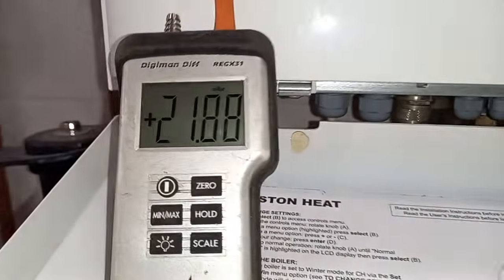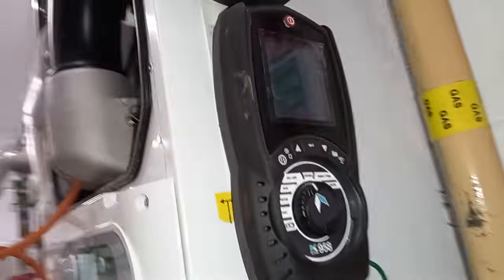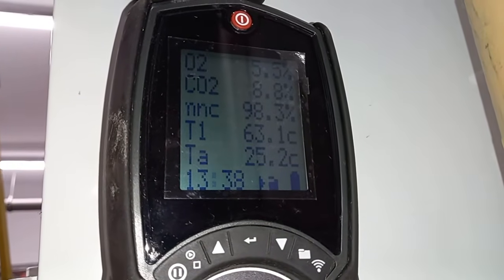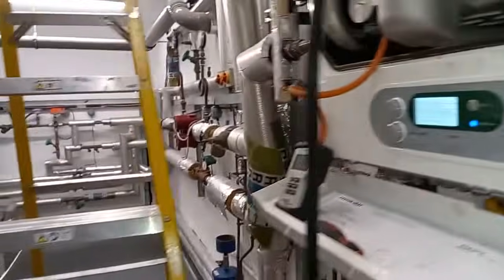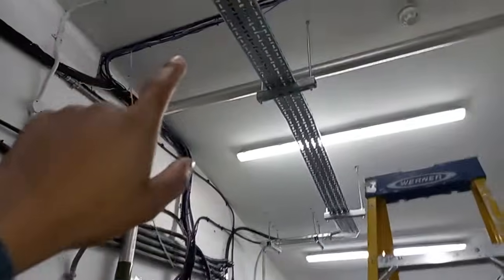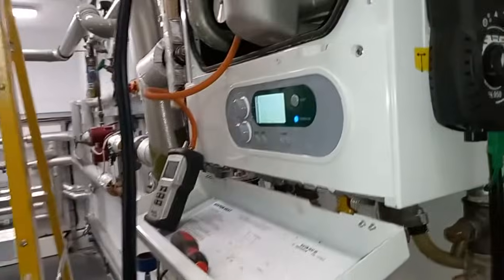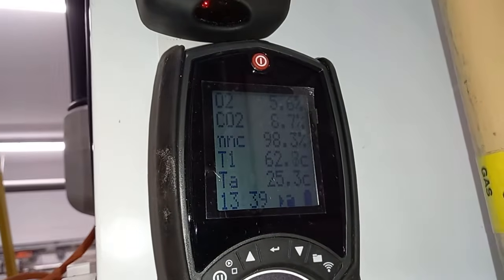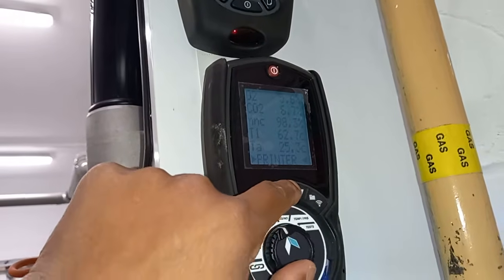See my working pressure? I've got the burner still on, but the working pressure has changed. And that flue temperature, T1, is my flue temperature. It should start dropping. You see TA is temperature ambient. So that is my temperature in the room. Remember to check your high, your mid, and your low position and make sure it's correct. So my flue temperature has started to drop. My CO2 looks good. So I'm printing out my second reading.